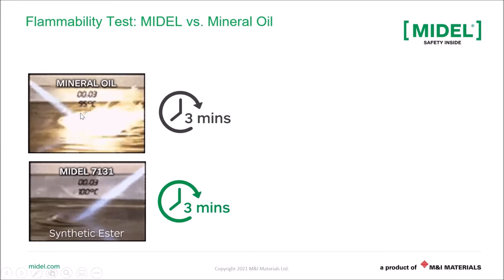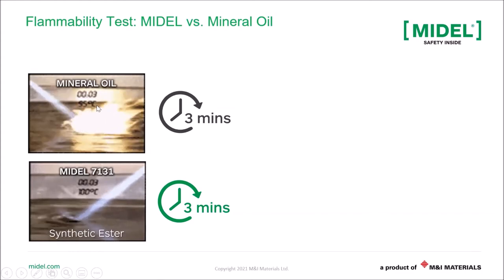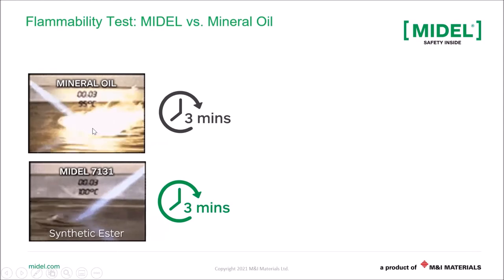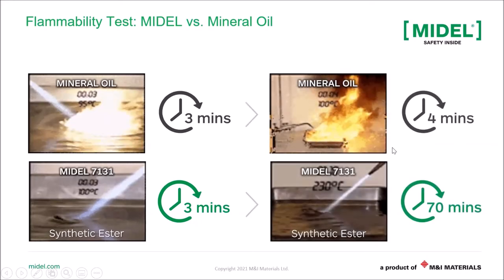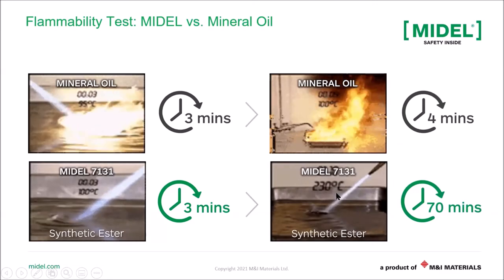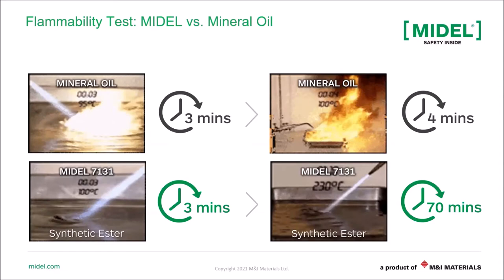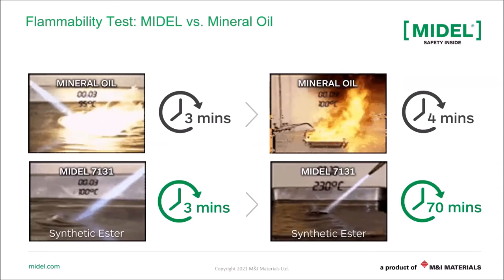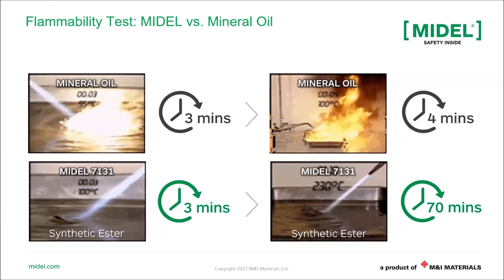So in this example here, there's a pan and there's an acetylene torch put on top of the pan. The pan is filled with mineral oil and MIDEL 7131, which is a synthetic ester. What you can see here is that at 95 degrees C, after 3 minutes, the liquid is already starting to catch on fire, whereas in the synthetic ester, there is nothing happening after 3 minutes. Now, when you look at the same pan at 100 degrees C, in 4 minutes, the pan has caught on fire with mineral oil. Whereas with MIDEL 7131, it's all the way up to 230 degrees C, and it's at 70 minutes, and there's no fire that has occurred yet. So this just goes to show the fire safety aspect of using an ester liquid.